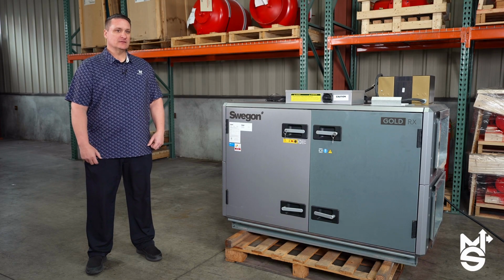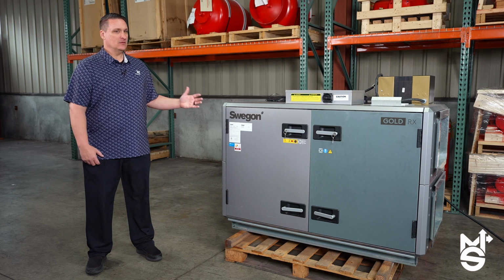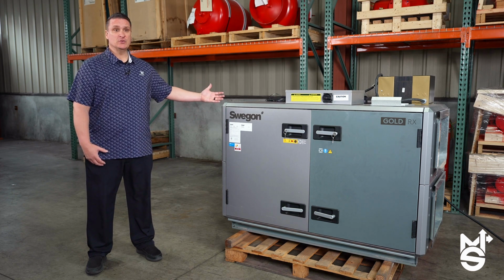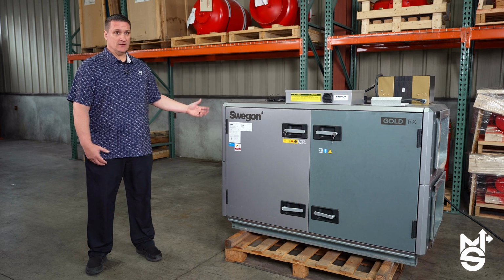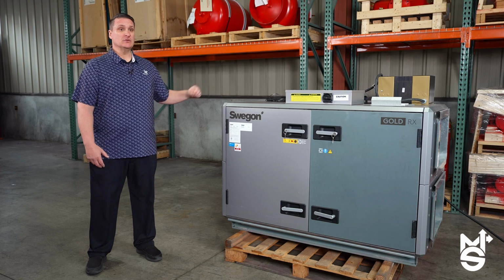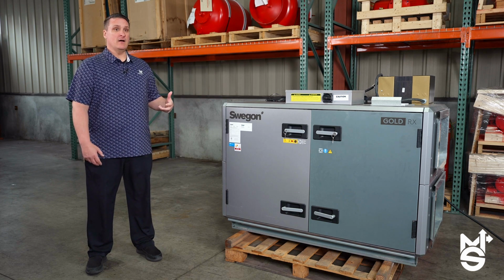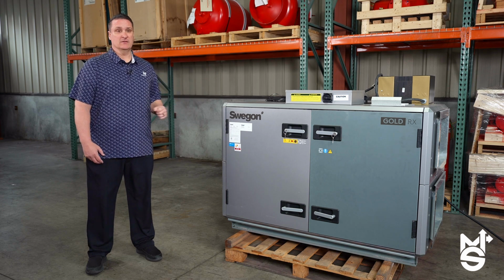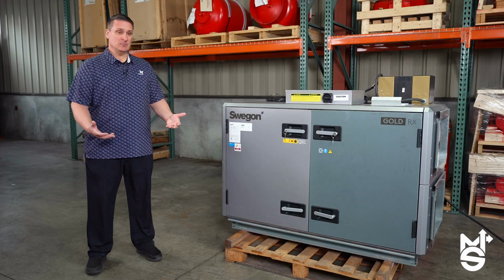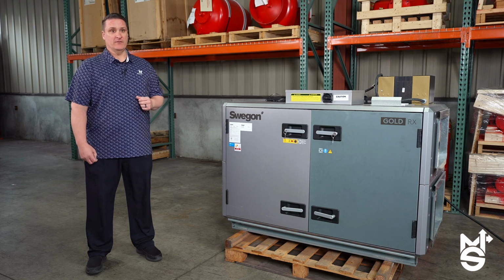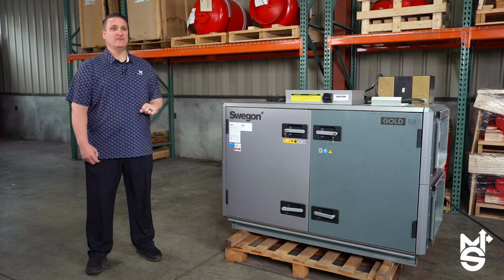Let's talk about installation benefits. The Swegon ERV has single-side access, meaning this unit can be mounted flush to a wall. Ductwork can be either horizontal or we can have all topside connections up to approximately 4,800 CFM. You can also choose between horizontal and vertical as well as a mix and match. Doors are mounted flush, swinging outwards, and providing complete access to all the components of the ERV. As the unit is constructed, it does not require external vibration isolation. In fact, it's not recommended. All these construction benefits allow the Swegon ERV to be installed inside a building and commonly next to occupied areas.